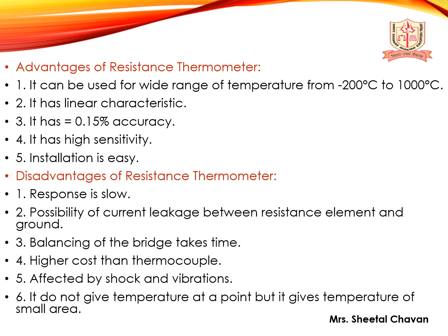Advantages of resistance thermometer. It can be used for wide range of temperature from minus 200 degrees centigrade to 1000 degrees centigrade. It has a linear characteristics. It has a 0.15% accuracy. It has a high sensitivity. Installation is easy.